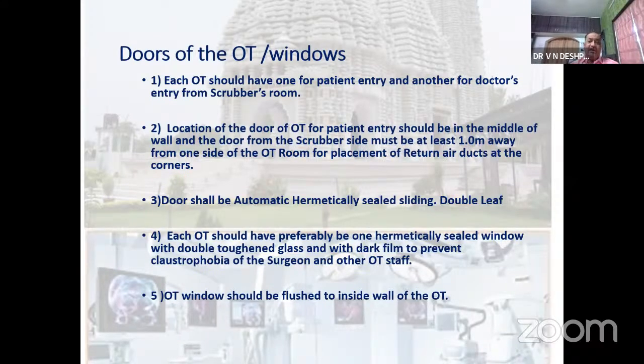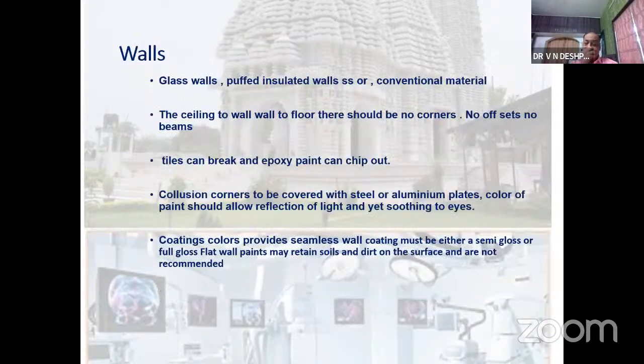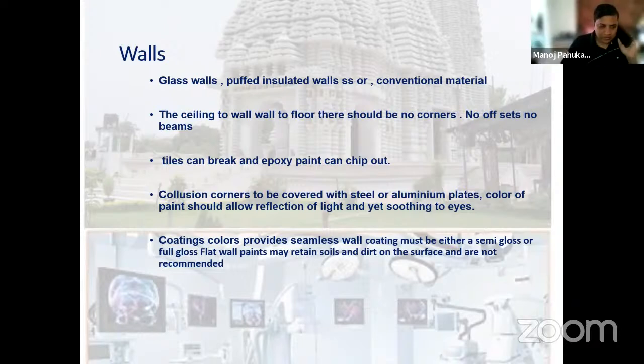Each OT should preferably have a window to reduce the claustrophobia of the surgeon. These days, with laminar flows, there are windows which are nicely designed and which create a virtual window-like effect. The OT window should be flush from inside, and it should have double glass, which should be toughened glass, and it should be screened with sun blinding films. The walls of the operation theater can be glass walls, puffed or insulated walls, or conventional material. From ceiling to wall and wall to floor, there should be no sharp corners. There should be no corners, no offsets.